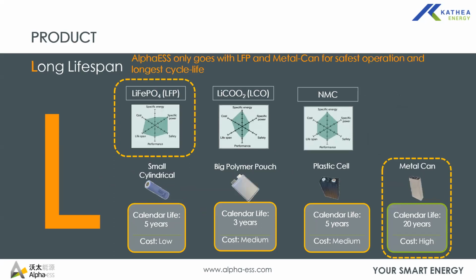And then the Alpha system uses the new technology. We all know lithium battery, lithium storage technology is up in the market. So it uses the technology, with its advantages of long lifespan and bigger depth of discharge. So the system utilizes that technology. The battery lifespan is pegged at approximately 20 years at an assumption of 1 cycle per day. So with an assumption of 1 cycle per day, the lifetime of the battery can go up to 20 calendar years.